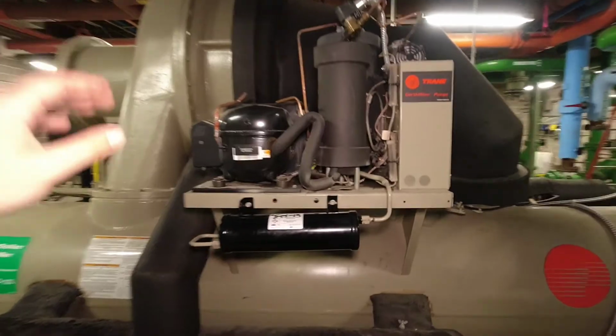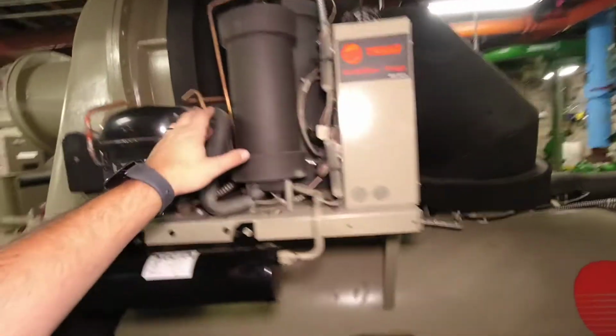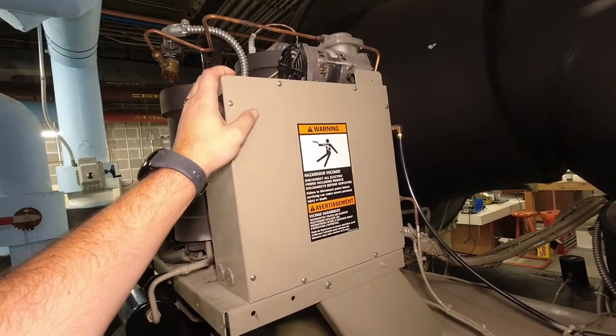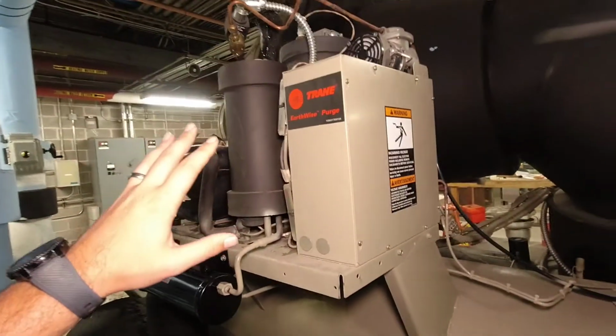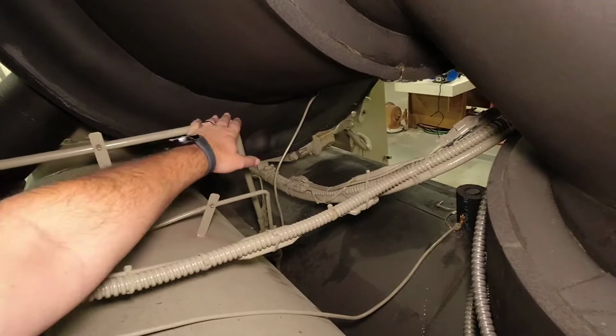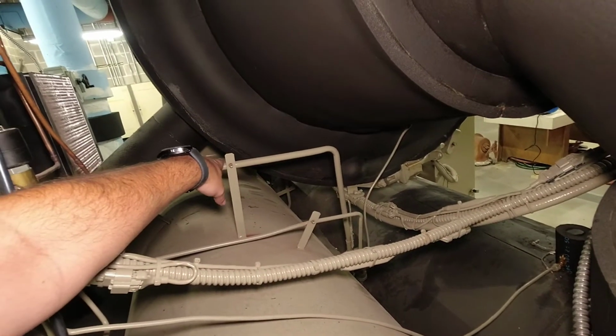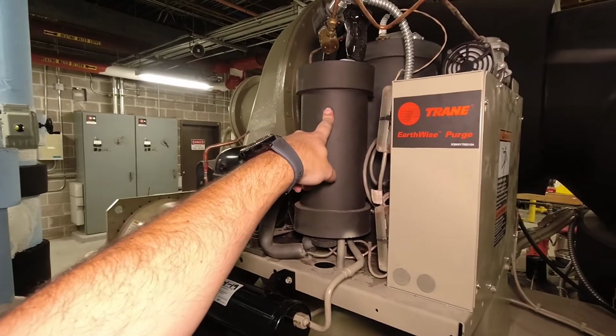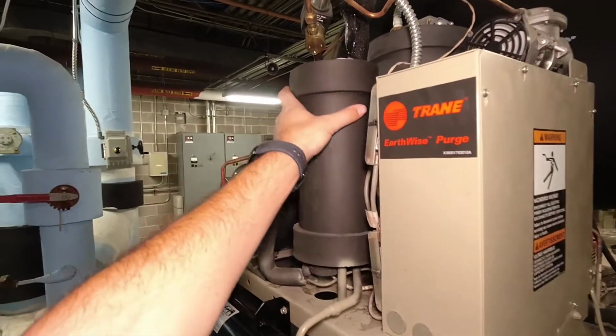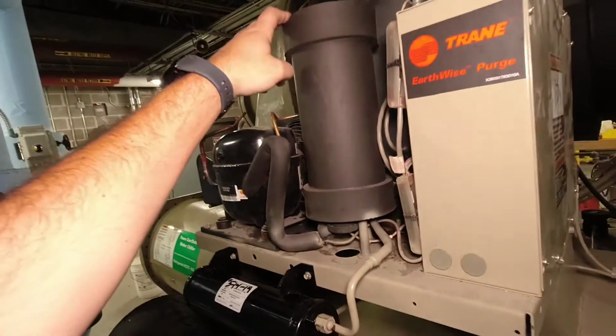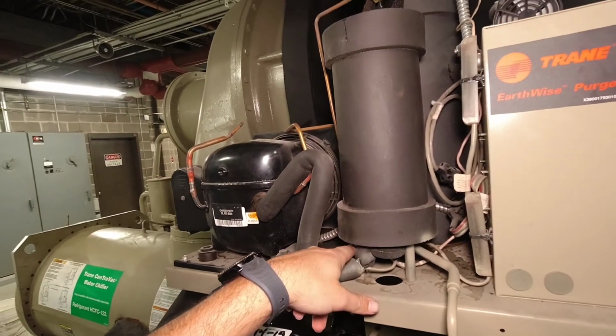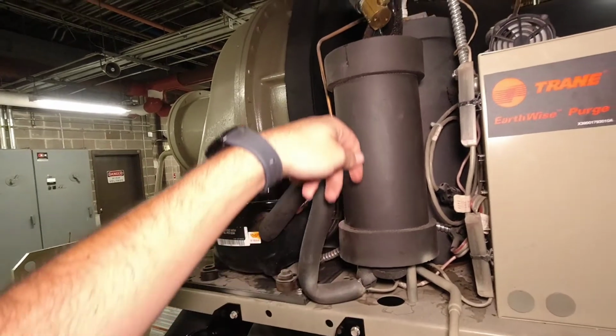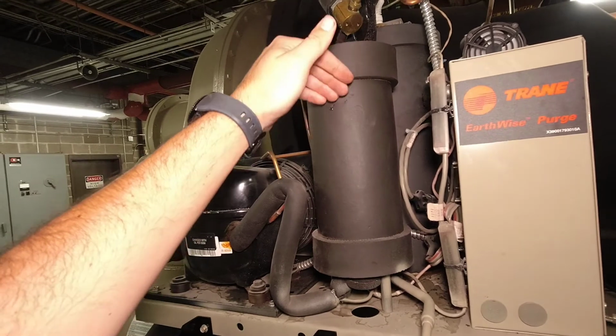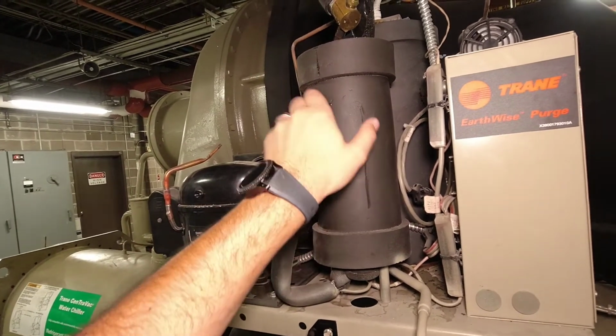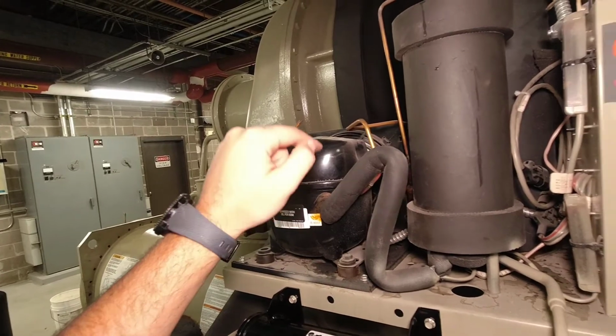The next item on the ticket is going to be our purge assembly, since we're here. So the purge unit's main function is to just purge any atmosphere out of the system. You have condenser gas coming up, and it is naturally going to come to the top of this reservoir tank. So this is actually a heat exchanger, and what we're doing is the condenser gas comes into the top of the tank, and there is a little coil inside of here that this compressor is cooling down.